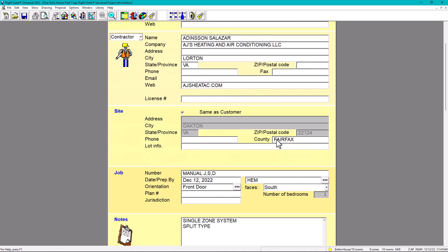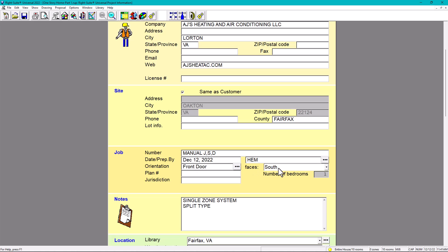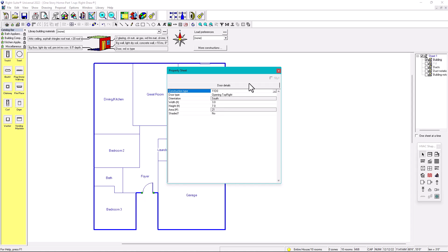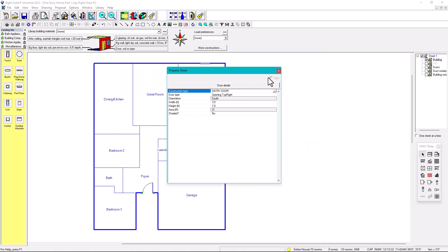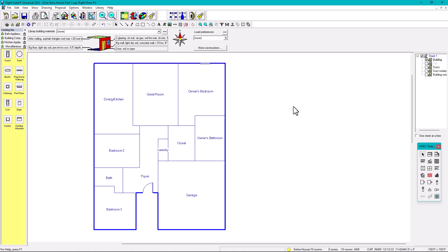Now let's go to the orientation. We said the front door is facing south. Going to the draw view, we need to draw our door first. We go to the HVAC Shapes toolbox, select the door, and place it at the front. This door is going to be three feet wide and seven feet high. In the materials we can set it to entry door, which gives us the U-values and insulation.